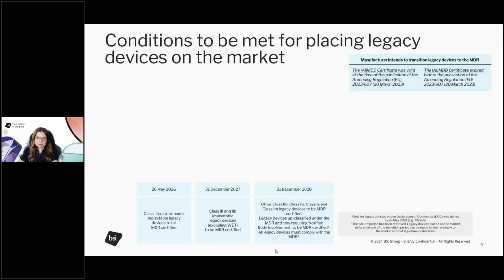But the end of 2028 is also the deadline, the end of the transitional timelines, for those legacy devices that were self-declared under MDD, but which are up-classified under the MDR, and therefore they do need to work with a notified body for the first time. So this means that after the end of 2028, all devices shall be in compliance with the MDR.